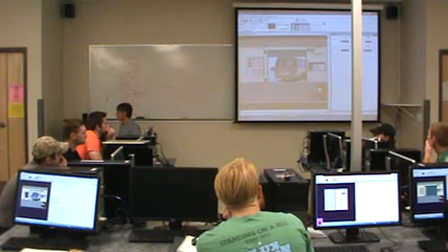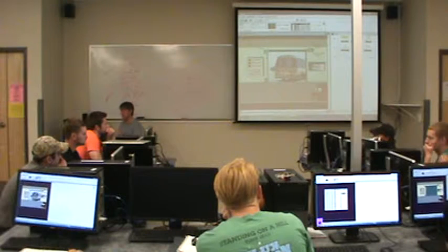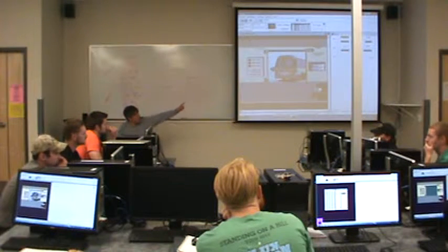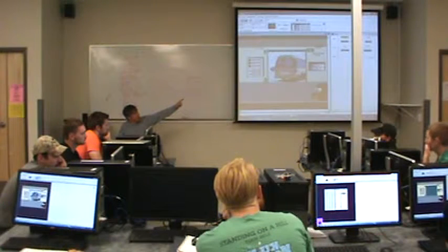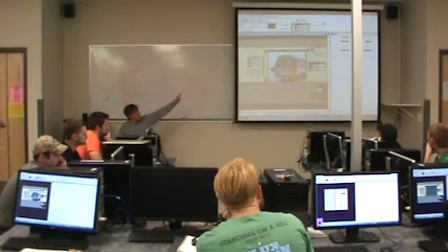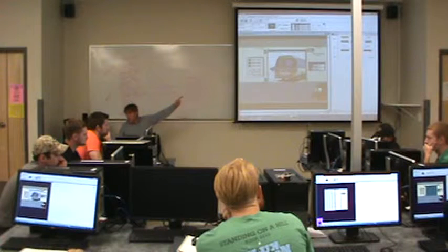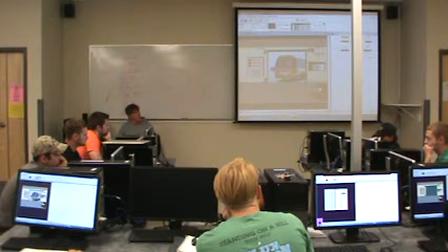Download, run, hit open. Even if I hold down the open button, the motor does not burn out, because notice what's happening. See how the open button is highlighted, meaning it's passing power? But see how input 3 is not passing power because that limit switch is open? Therefore, the power cannot get to the motor up winding.